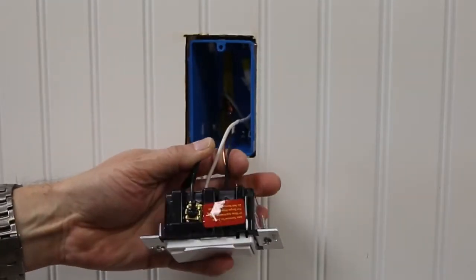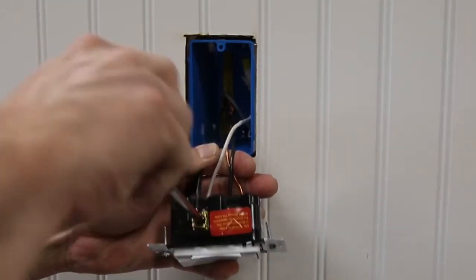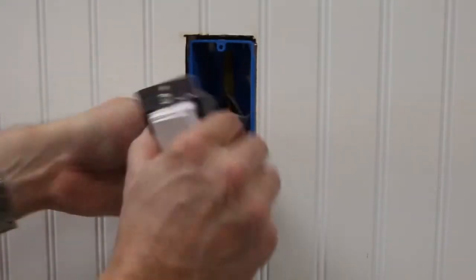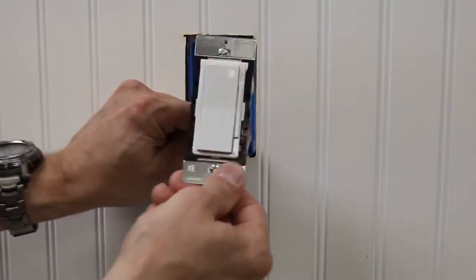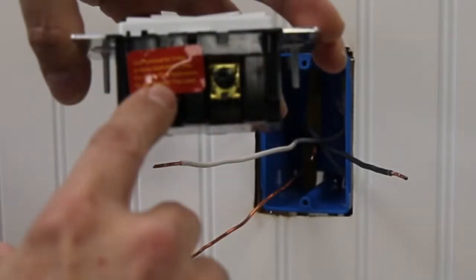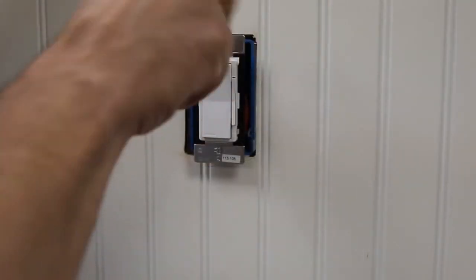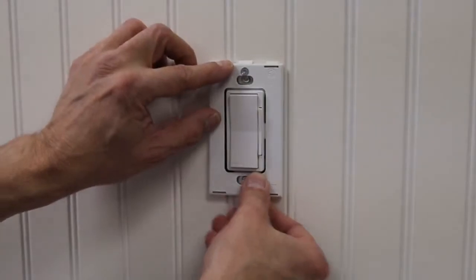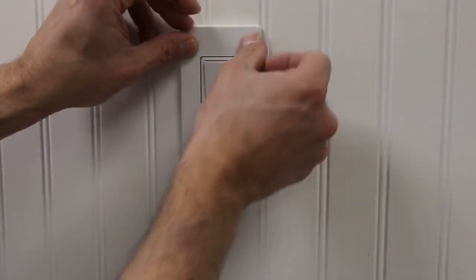Note, each terminal can accommodate back wiring for up to 2 conductors. Connect the line hot wall box wire to the terminal screw marked BK. Tug on all conductors to ensure the termination is secure. Note, switch terminal screw marked YL/RD should have red insulation label affixed. If the insulation is not affixed to terminal screw marked YL/RD, use electrical tape to cover. The device is now terminated. Complete the installation by tightening the mounting screws into the wall box. Install the wall plate, switch the power back on at the circuit breaker.